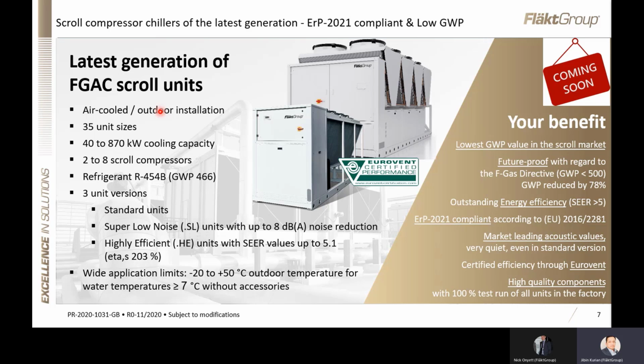We already have an existing range, and today I'm going to talk about our new range, which will be launched in December 2020 and is more efficient than our previous version. These ranges are available in 35 unit sizes, with capacities varying from 40 to 870 kilowatts, and 2 to 8 scroll compressor designs, with refrigerant R454B with a low GWP of 466.